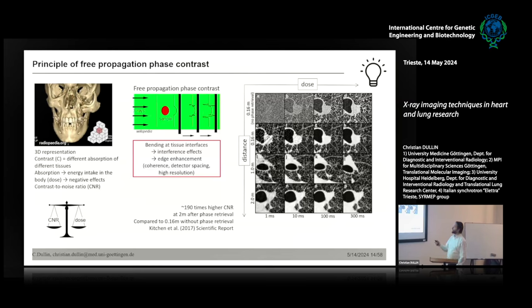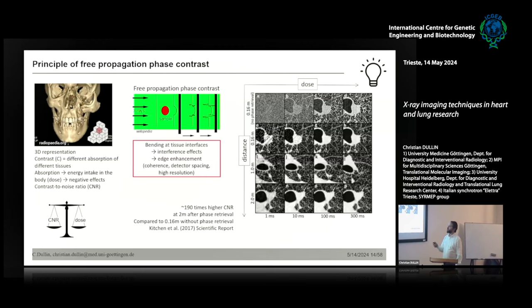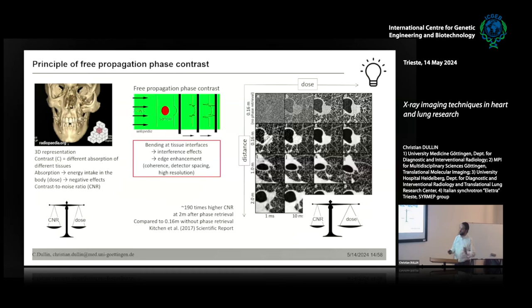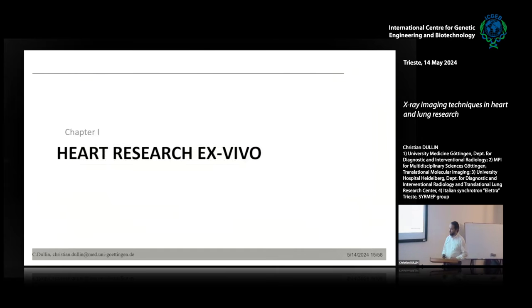This is a nice study from Marcus Kitchen in Australia using rabbit lung. If you don't use many x-rays you get a noisy image; if you use more and more x-rays you get a decent image, but that means a lot of dose for your subject. If you just move the detector away and do some post-processing, you get very nice images at the same dose level — with two meters of propagation distance. Comparing at the same x-ray dose: one without phase contrast, one with phase contrast. This already tells you why I'm interested in doing this in patients.